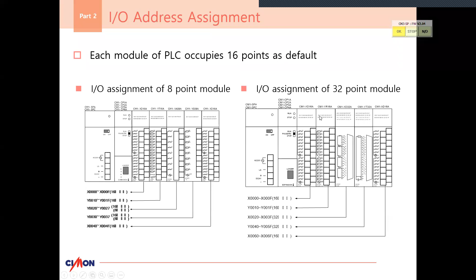When we talk about expansions and address assignment, the main thing I want to cover is that when you get your expansion module, you notate which expansion it is with a little rotary feature. You declare what expansion it is in line - say you had expansion E, that would be 15 - and you'd only want to use it in the spot of expansion 15, not at location 3 or 2. You want everything in numerical order, 1 through 16, since the max is 16 for expansion on the XP and CP series, and soon for the PLCS when we finalize our expansion module for remote IO. But for right now, it's just the XP and CP series.